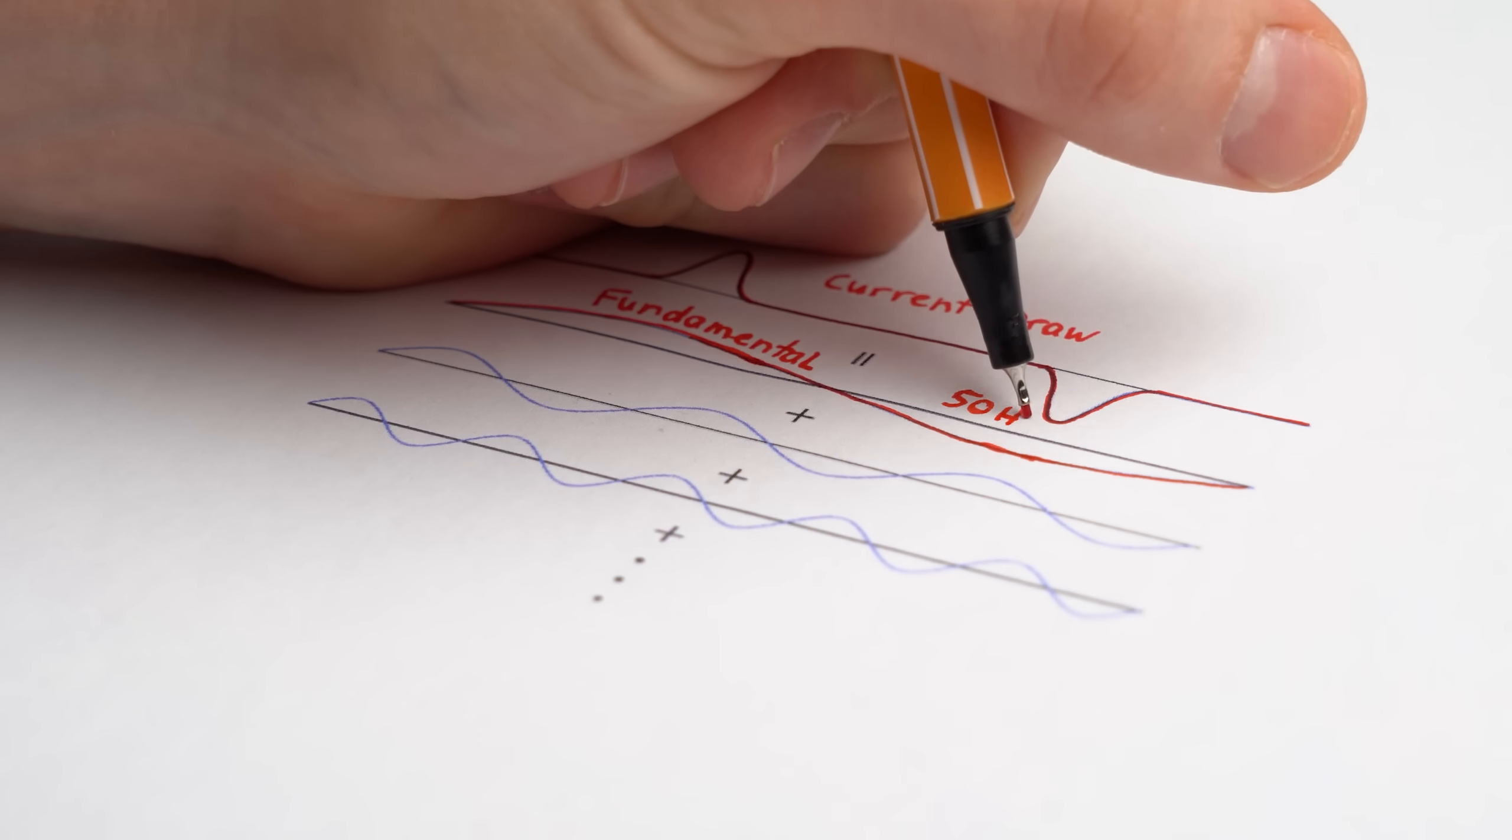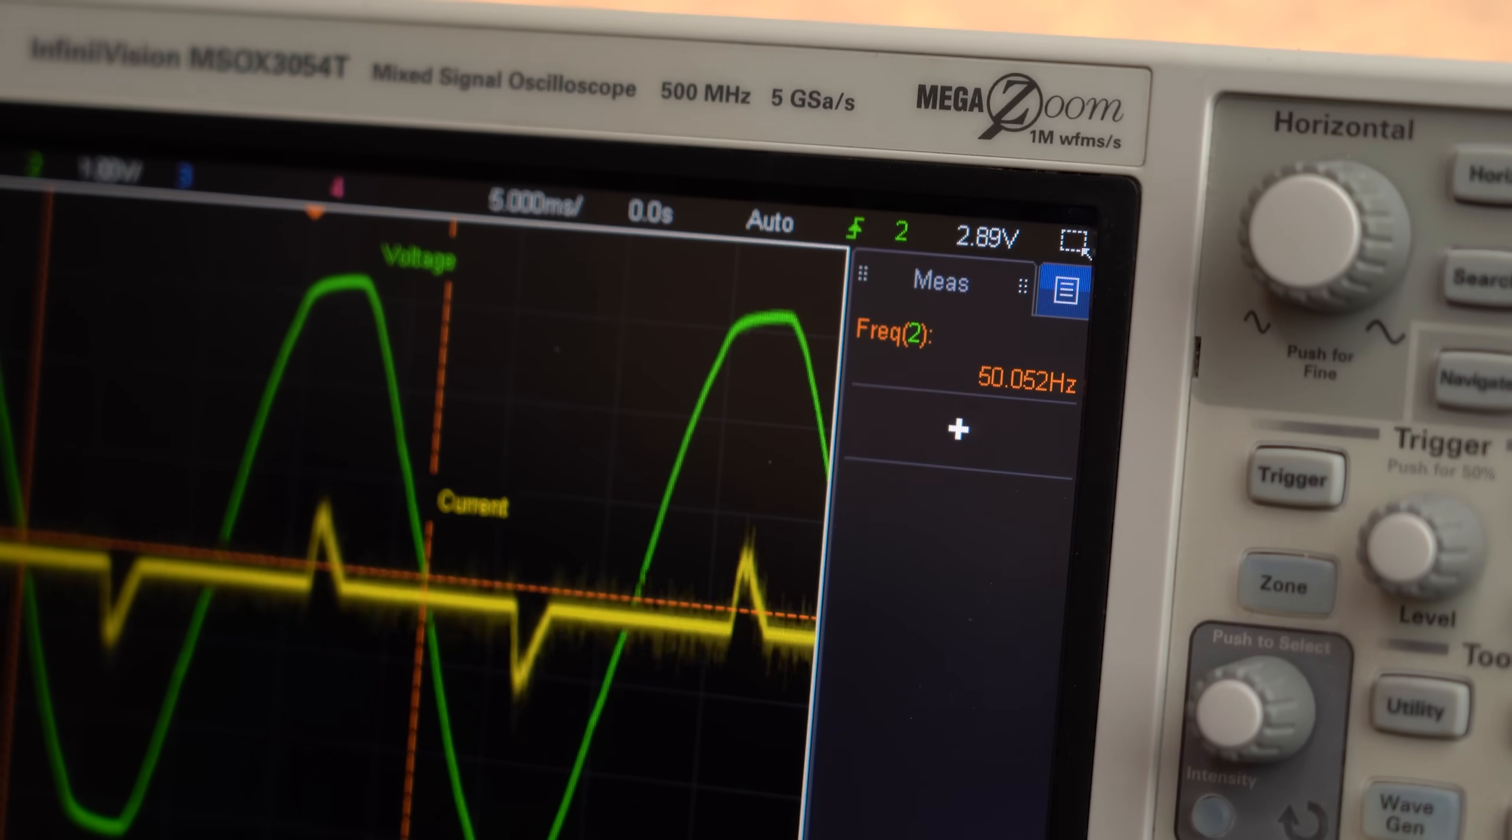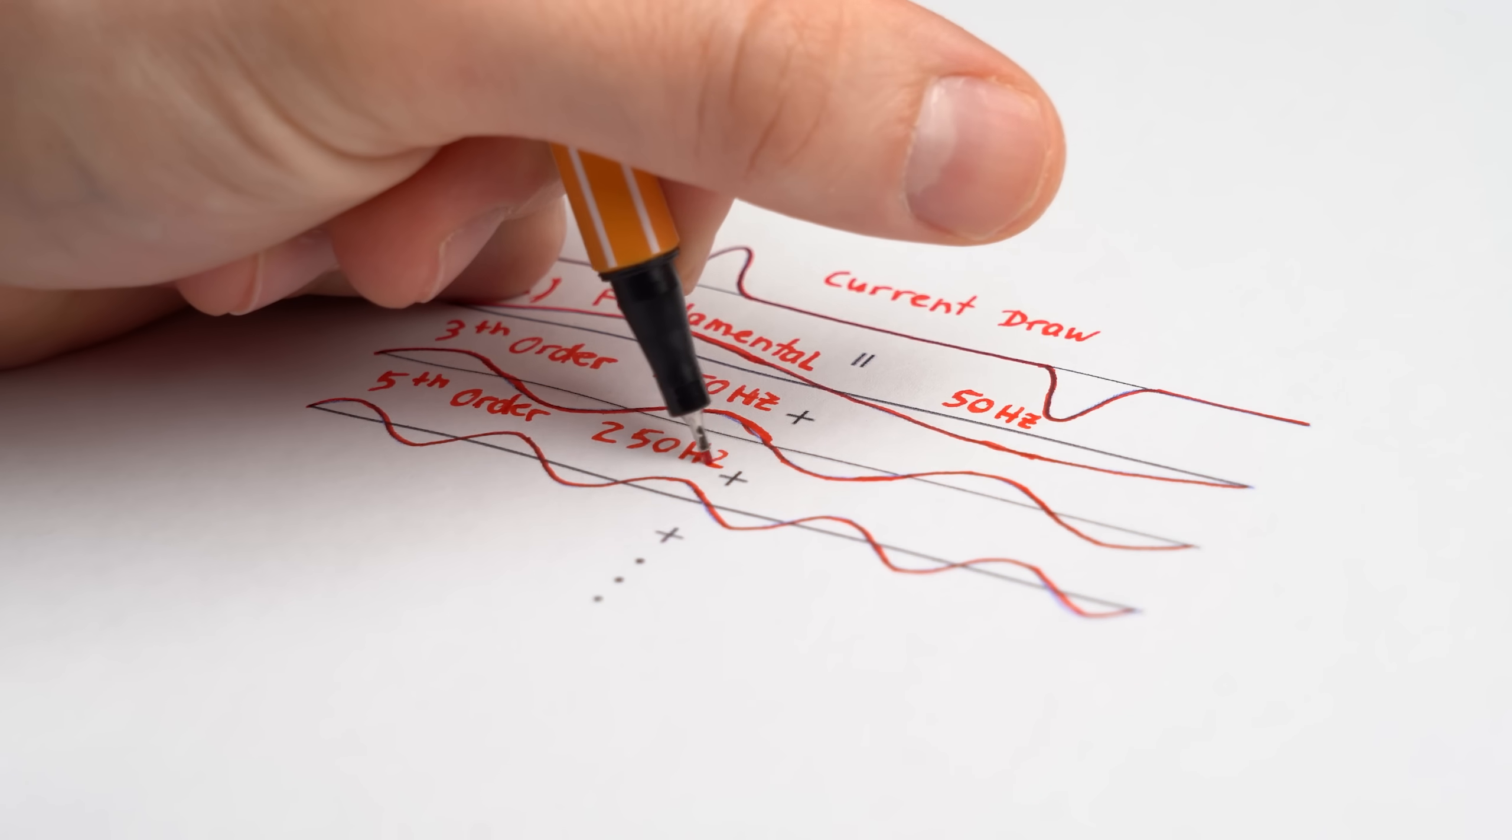Well the problem here is that this current waveform can be depicted as a sum of lots of current waveforms with different frequencies. Most importantly of course is the 50Hz fundamental frequency which is our mains voltage frequency and it obviously does not feature a phase shift. But then there are also 150Hz, 250Hz, 350Hz and so on parts which are called 3rd, 5th, 7th and so on current harmonics.